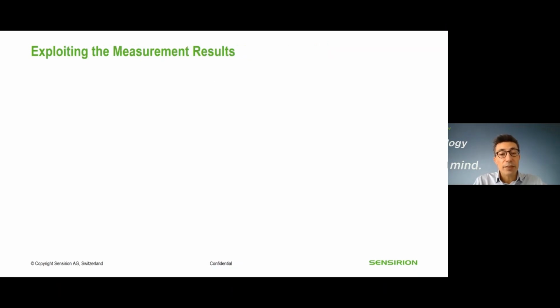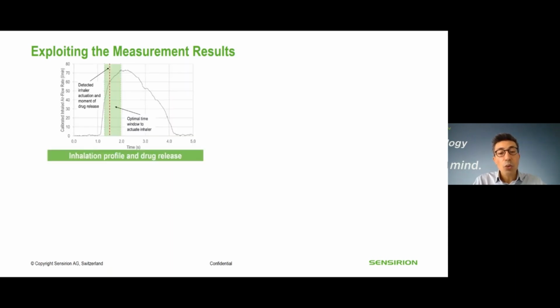The calibrated results are sent from the clip-on sensor to an application on a smartphone, which exploits the results numerically. In this curve, we can see the inhalation profile of the patient over time. The optimal actuation window can be identified on the curve shortly before the peak inspiratory flow rate. The accelerometer that we included in the clip-on sensor detects the actuation and moment of drug release. The moment can be compared to the optimal actuation window in order to conclude whether the actuation was performed correctly.